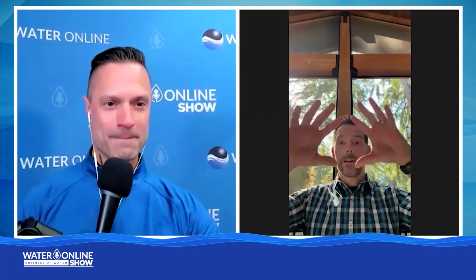So would you be able to give us a quick summary of the pros and cons of each of them? Yeah, absolutely. Each has their own benefits and drawbacks. I would say the biggest benefit of the internal cone is that it has more nozzles than any of the other designs. It has about 1 per square foot of cross-sectional area. You can imagine that a lot of nozzles means a lot of flow paths, right? A lot of potential paths for the water to take. That means good distribution over the bed of the media, which means good media utilization.